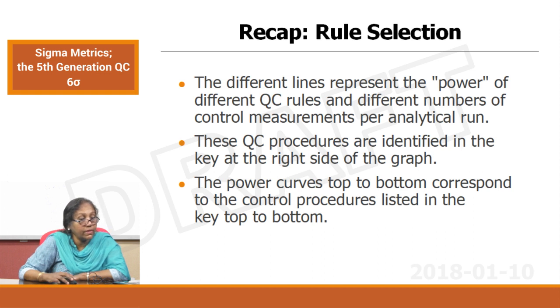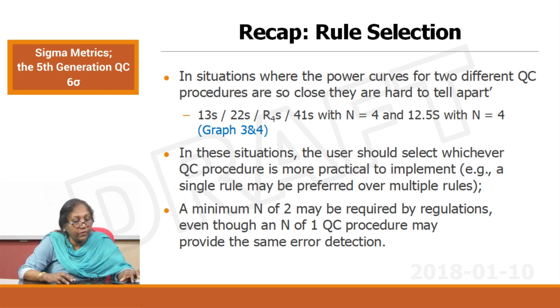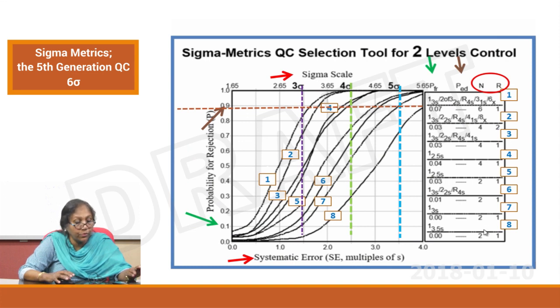To recap about rule selection: different lines represent the power of the different QC rules and the different numbers of control measurements per analytical run. These QC procedures are identified in the key at the right side. The power curves from top to bottom correspond to the control procedures listed top to bottom. In situations where the power curves for two different QC procedures are very close — as in graphs 3 and 4 — the user should select whichever QC procedure is more practical to implement. A single rule may be preferred over a multiple rule if you are able to monitor it adequately. A minimum N of 2 may be required by regulations even though an N of 1 QC procedure may provide the same error detection.